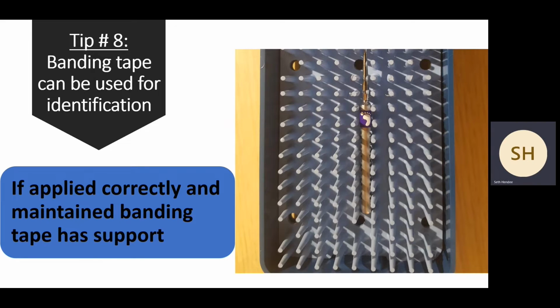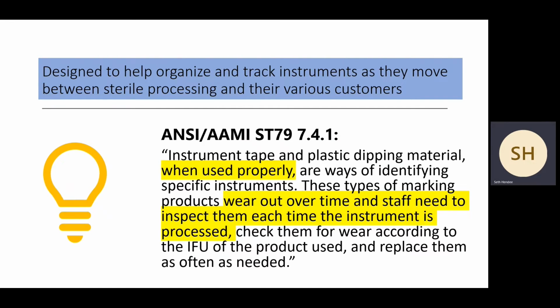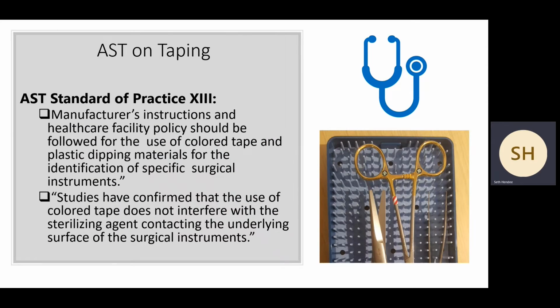Here's the thing: if applied correctly and maintained, it does have support. Okay. ST79, section 7.4.1. When used properly, you can use plastic dip or instrument tape, but these types of markers wear out over time and the staff need to inspect them each time the instrument is processed. If you cannot guarantee that that's happening, you probably shouldn't have tape within your department. What about AST? That's, again, it's not just AAMI necessarily.